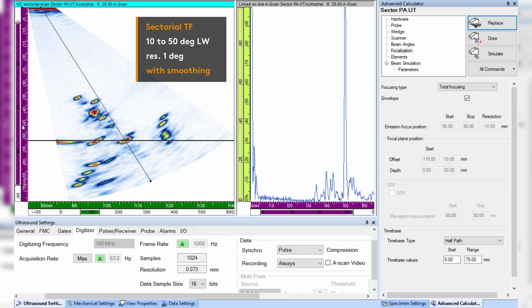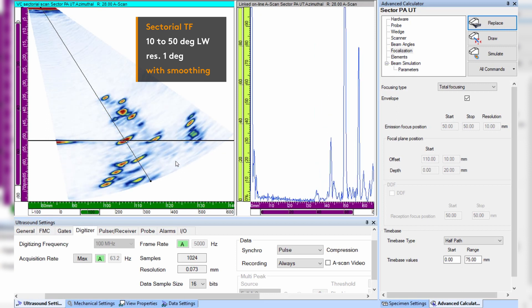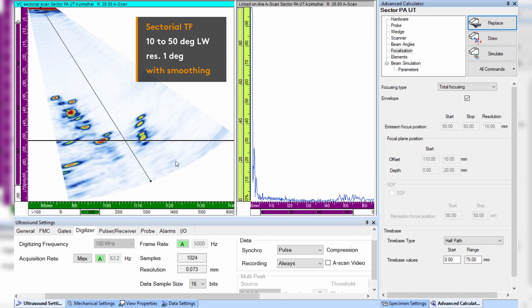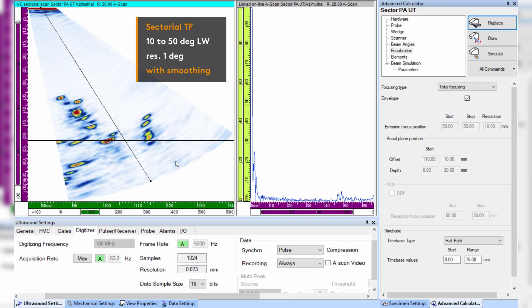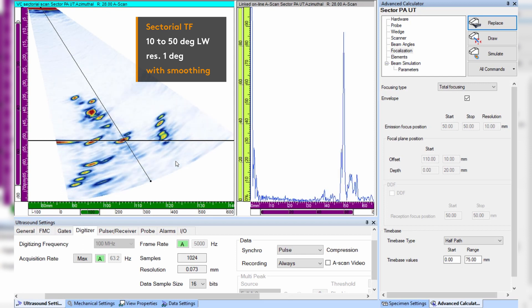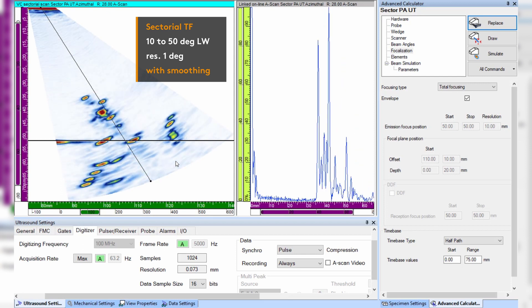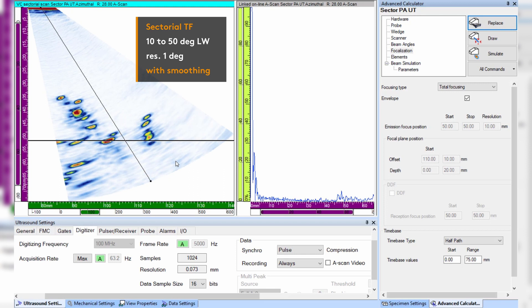We can immediately see that sweep with total focusing provides efficient focusing in a much larger region. Just like TFM, it allows to keep both flaws perfectly in focus at the same time.